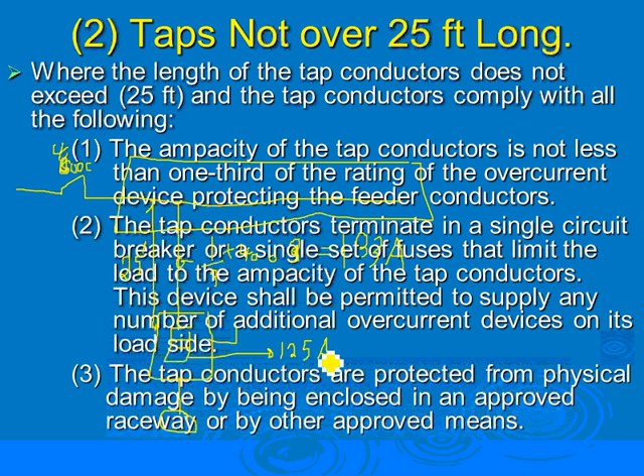What happens if you don't have a standard circuit breaker size? I always say you custom design one by Bussmann. You have to give him one of your legs and an arm with it, or you can go down. That 125 is the maximum, right? You're sizing that fuse down below, right? Yes. Everything is, this is the minimum conductor, and this is the maximum overcurrent protection device. You can't put a bigger conductor and then put a bigger fuse. You got it. You got it.